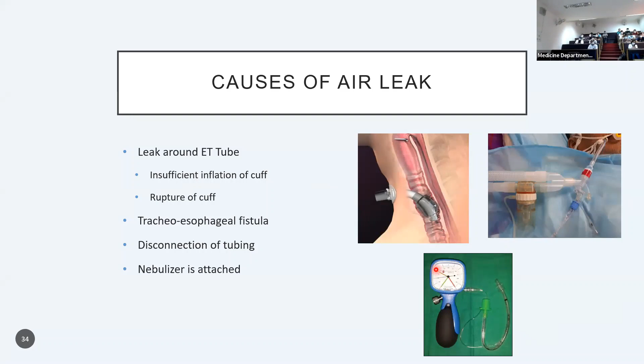And how can we measure this? Insufficient inflation of the cuff: whenever you intubate a patient, it's always good to connect the cuff monitor which we have in our wards and C2 ICU to the pilot balloon so that you can see that adequate cuff pressure has been achieved. Adequate cuff pressure is around 20 to 30 centimeters of water, and it is reflected as a green area in the cuff monitor. So the cuff pressure should be neither too high nor too low. Another technique is the minimum leak technique, which also ensures adequate cuff inflation.